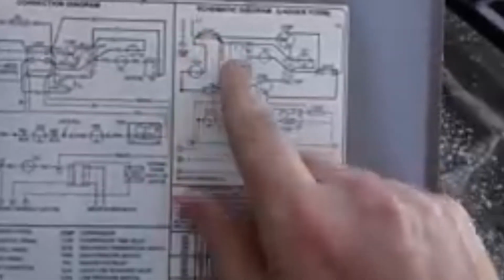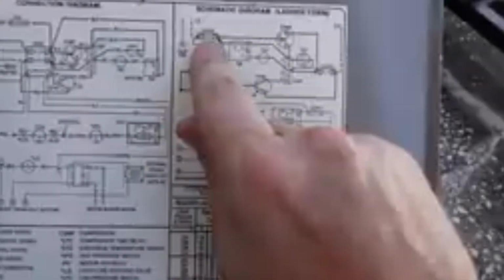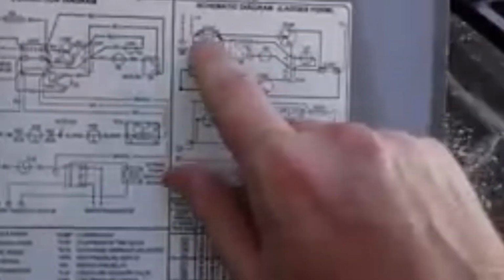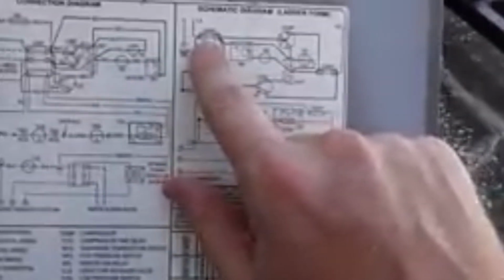In the case of this contactor, it only has a single pole, which means as this switch opens, it shuts off the entire unit. We can check for voltage drop across that point, and it will measure the total applied voltage when the contactor is de-energized, and it should show next to no voltage drop when the contactor is energized.